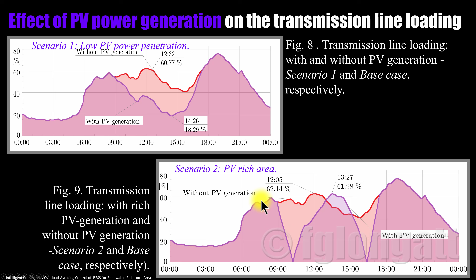However, when we have the PV rich area, I mean we have a huge power plant connected to the bus bar number 3, the situation starts to be quite interesting, because this change on the direction of the power flow at the transmission system create a very interesting situation. As you can see here, around 8 a.m., the PV power production starts to increase and pick up, and you can see how the loading of the transmission line is decreasing. Then, when we have enough PV power generation, you can see how the reverse of the power flow at the transmission line increase the loading of the transmission line here. And that is quite interesting.